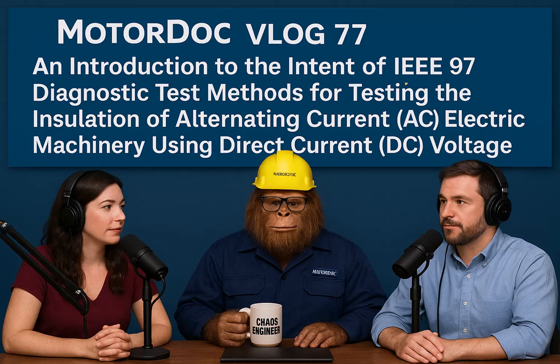Finally, you have the conduction currents. These sound like the ones you don't want. The leakage. Well, yeah, they represent the leakage pathways. Conduction current is the sum of surface leakage current flowing over the outside surfaces and volume conduction current flowing through the bulk material itself. And these just keep flowing. As long as the voltage is applied, yes. They're continuous, irreversible. Ideally, for healthy, brand new insulation, these conduction currents should be negligible, tiny. Okay, so fast capacitive, slower material absorption, and the continuous leakage or volume conduction.